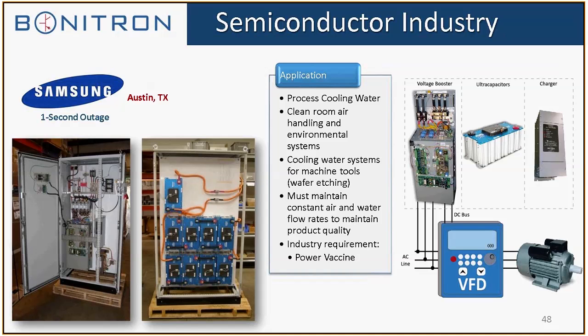This is the ride-through we did in Austin, Texas for Samsung. As I said, they have the vaccine spec, which is definitely a greater spec than SEMI F47. Energy storage, one cabinet, all the components in the other cabinet. It was for cooling water systems for machine tools, 150 kilowatts for 1 second.